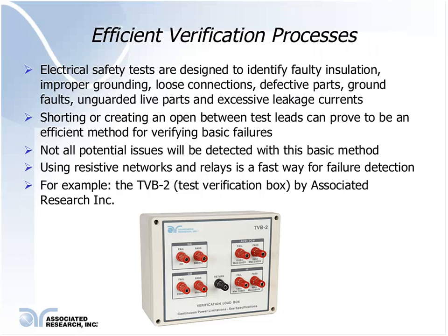Additionally, building such a network with easily accessible parts and programmable control allows a verification to be run automatically with each verification process, makes running the verification test much easier, and providing the operators and technicians with a simple means of verification basically increases the chances that any problem with equipment measurement will be caught prior to product testing.